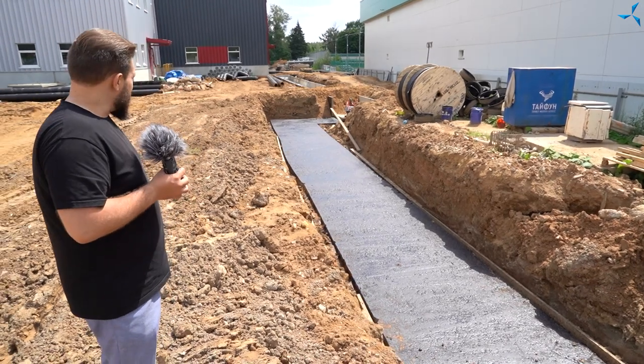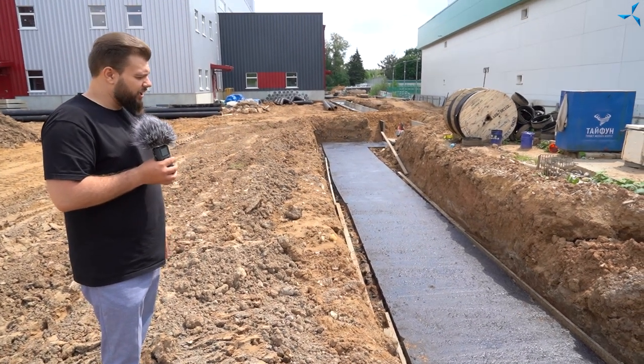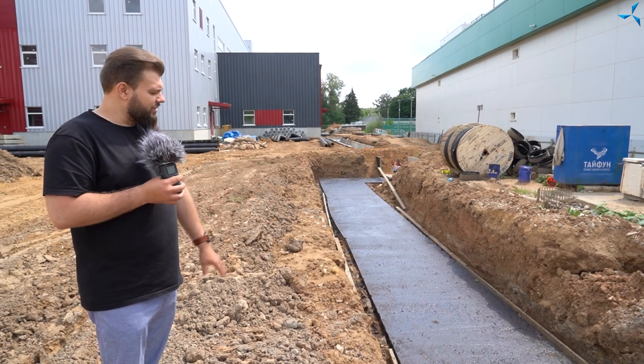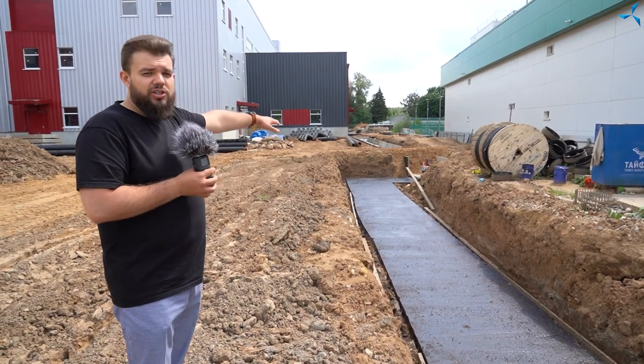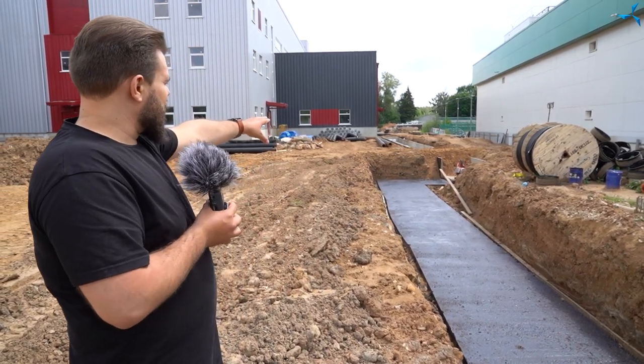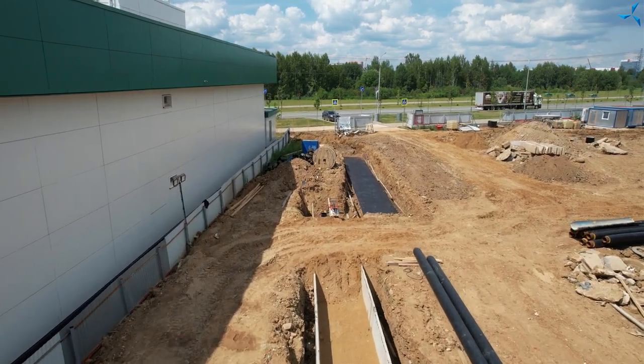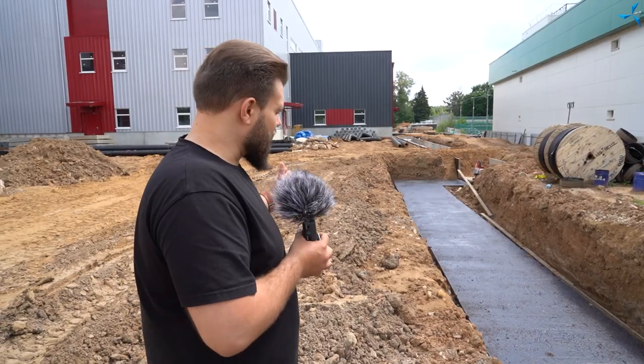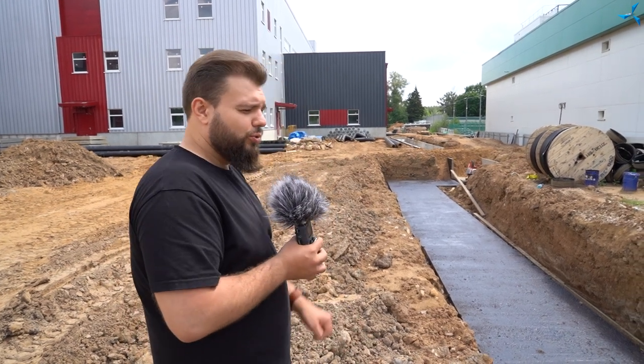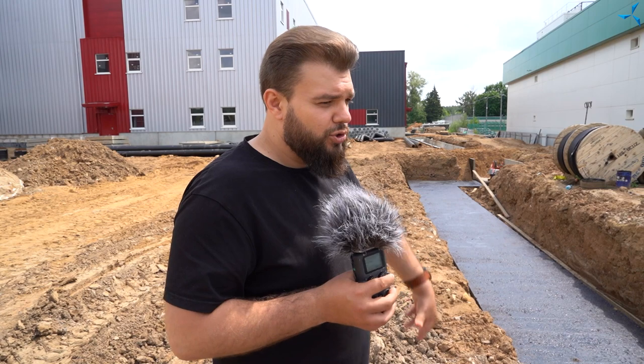These are heating mains. The sub-concrete has been done, and before that the ground was excavated, the trench was dug, the formwork was installed, then the sub-concrete and the waterproofing. We are now waiting for the delivery of the trays and will continue to lay them. In the part that is now coming to your screens, there has already been backfilling in some places. In accordance with the technology, waterproofed trays were installed on the sub-concrete, also waterproofed on the outside, filled in with sand, tamped down with a vibratory plate, and pipeline systems were laid. Connections, joints, compensators, and welding have been completed, and now we are waiting for outputs.